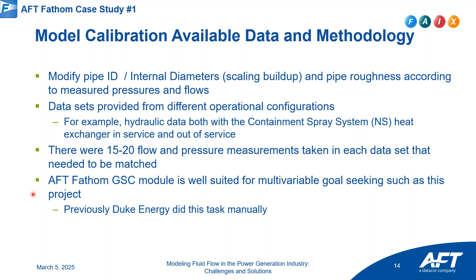As far as I'm aware, AFT Fathom and the GSC module is the only software in the market that can actually do this kind of a project: automated multivariable goal seeking to try to match the scaling and the pipe roughness versus measured flow and pressure measurements. And so this was done at the time back around 2013, 2014.